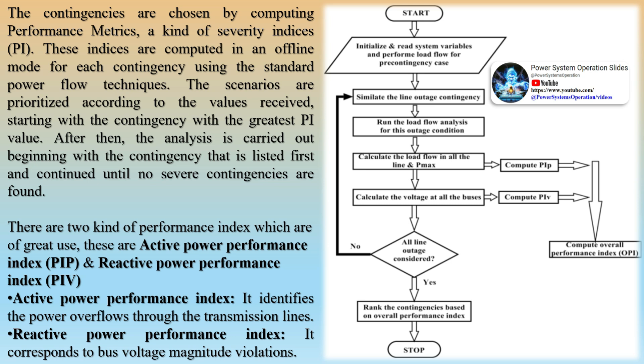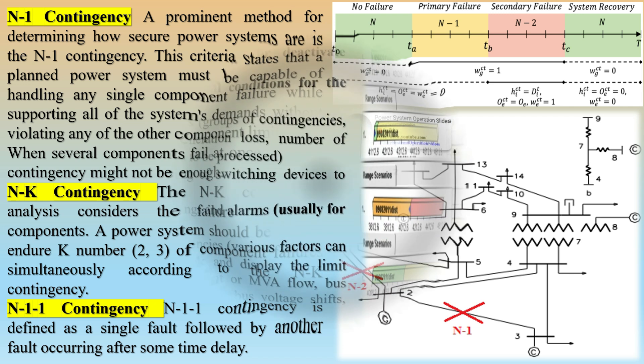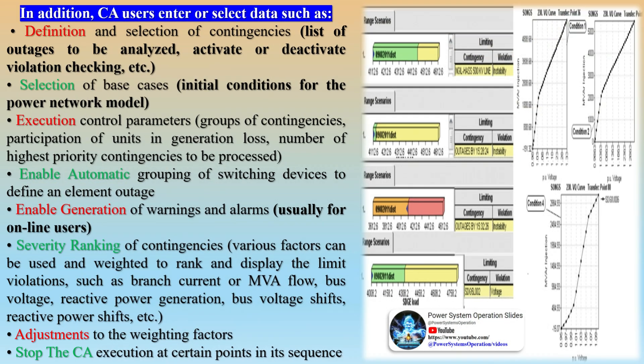Contingency analysis in power systems is a critical process used to predict and evaluate the impact of potential failures or outages on the electrical grid. It involves simulating various what-if scenarios such as the failure of a generator, transmission line, transformer, or load to understand the effects on the system's stability and reliability. Key aspects include: predicting equipment failure and taking corrective actions before the system becomes unstable; using security performance indices to assess system safety and rank contingencies by severity; and simulating outages to examine load flow or short circuit impacts after removing components like transformers, buses, and lines.